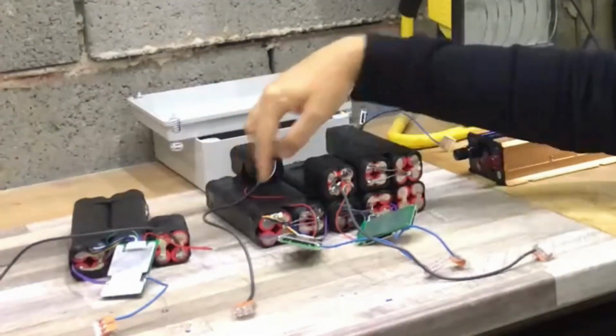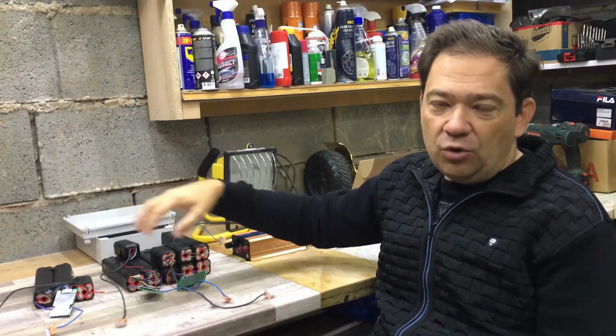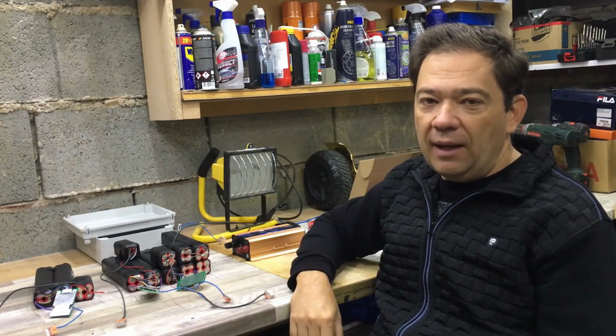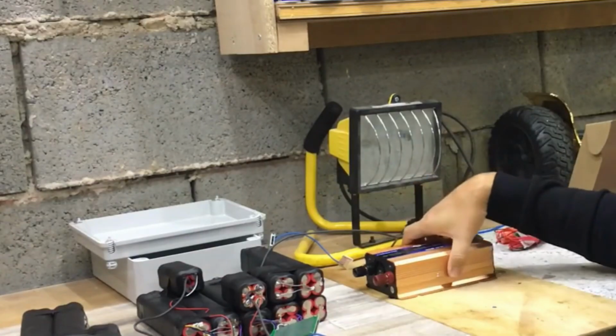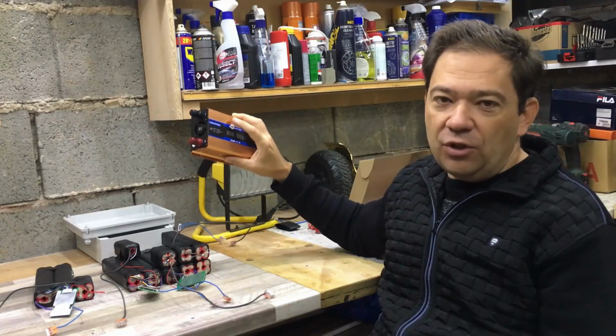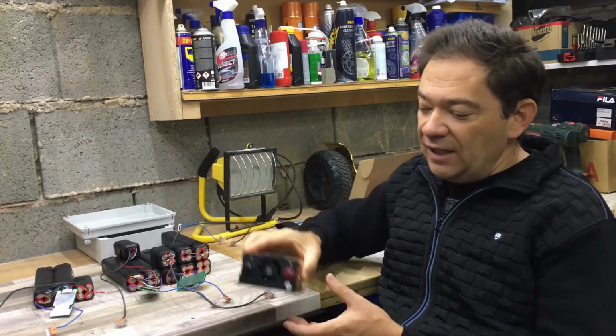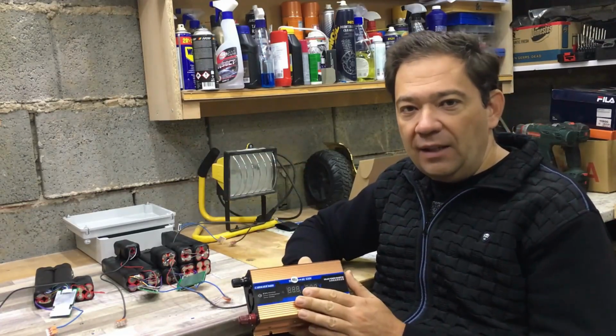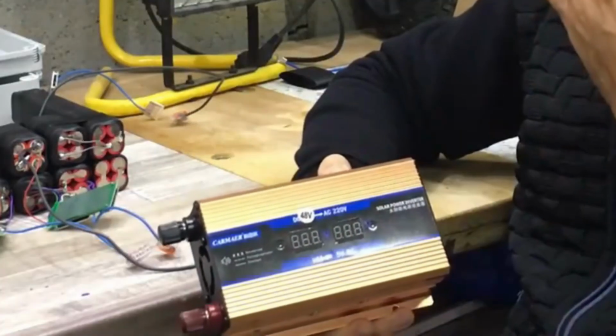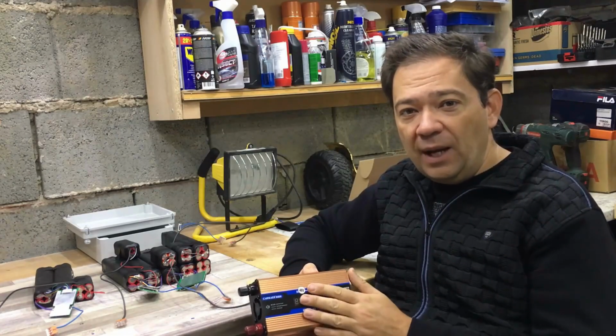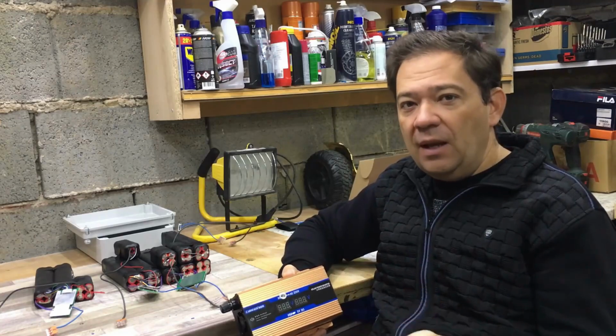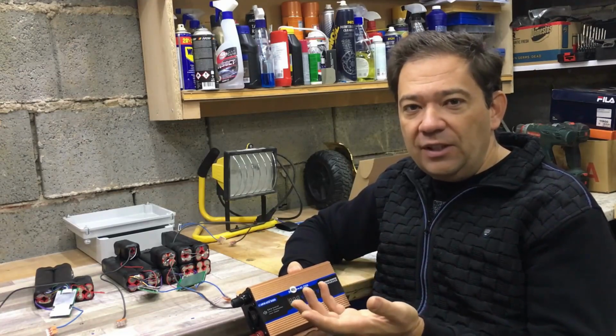I'm going to connect 2 banks in series and the other 2 banks in parallel with these, and that way, instead of 48 volts, I'll actually get 56 volts. But that's still perfectly fine for this inverter, because it's designed as if there were 4 12-volt lead-acid batteries connected in series. Fully charged 12-volt batteries are actually 14 volts, and 4 of those in series make 56 volts.